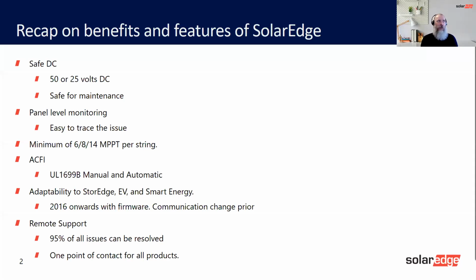So as I said, one of the benefits is that at the module, if you do fit an optimizer, as you know, that optimizer controls the current, it controls the voltage from the module. So this is a great feature, and this is the Safe DC feature. This allows us to send a signal, or to stop the keep alive signal, I should say. So every time the inverter is on and we are producing, every 40 milliseconds, you have a signal sent from the inverter to the optimizers to tell them to keep alive, to stay on.